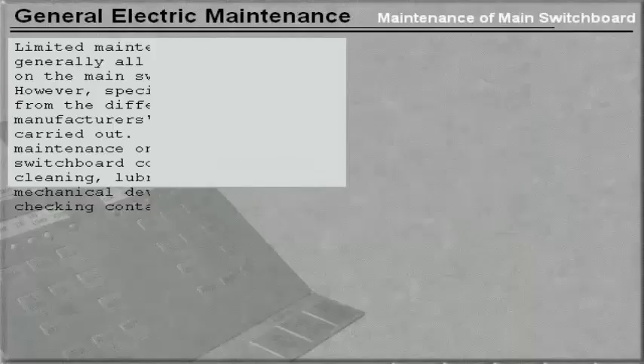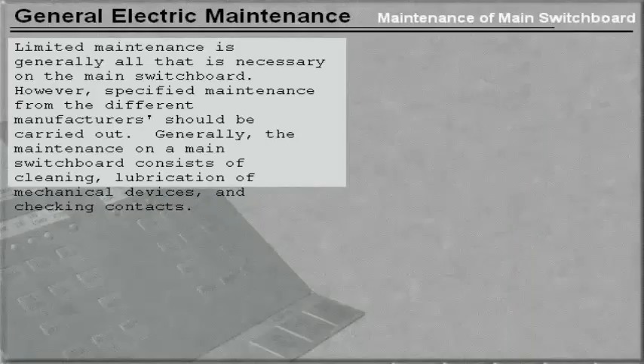Limited maintenance is generally all that is necessary in the main switchboard. However, specified maintenance from the different manufacturers should be carried out. Generally, the maintenance on a main switchboard consists of cleaning, lubrication of mechanical devices and checking contacts. Note that unnecessary tightening of contacts and terminals is not recommended. This may cause deformations and in turn break or weaken contacts.